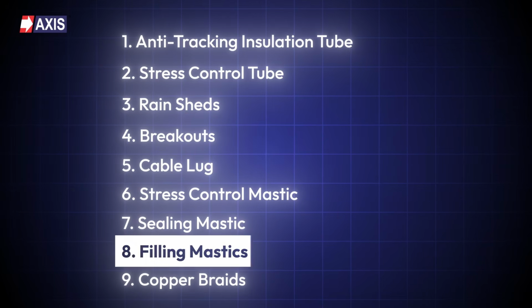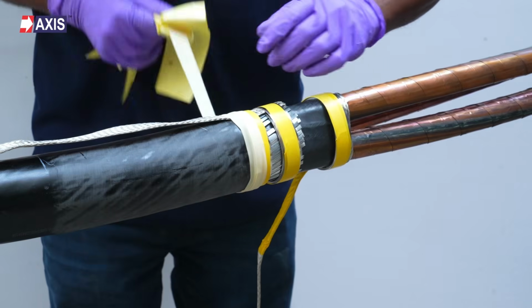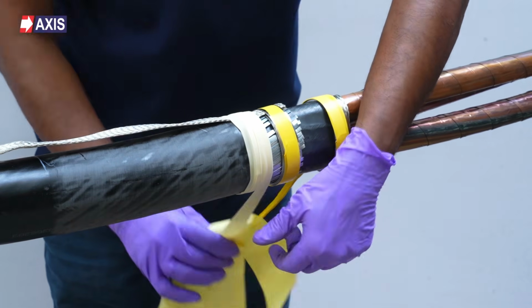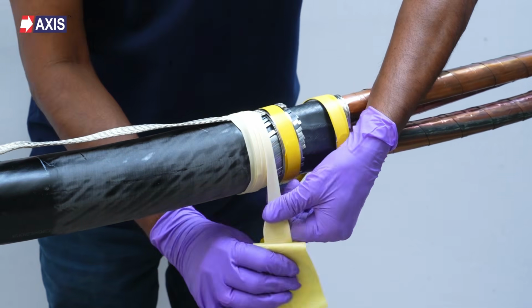Now, number 8 are the filling mastics. These are used to smooth out irregular surfaces and eliminate voids within the termination buildup. They help create a uniform insulation profile, which is essential for even electrical stress distribution. By removing air pockets and sharp transition, filling mastics reduce the risk of partial discharge and improve the long-term reliability of your termination.